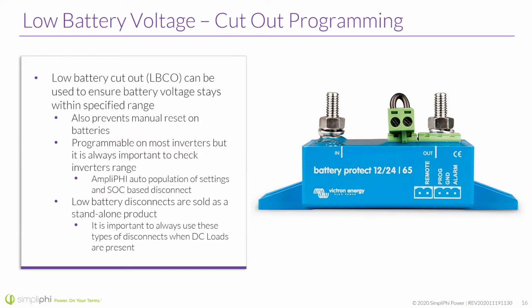It's programmable on most inverters, but it is always important to check inverter range. Some of the older inverters might not be able to hit the specified low battery cutout that we're talking about. So for instance, if we're looking at, let's say, a 48-volt battery that has 48.0 volts as the maximum low battery cutout. I know it's kind of confusing to say maximum when I'm talking about the low voltage, but this is the best way to put it.